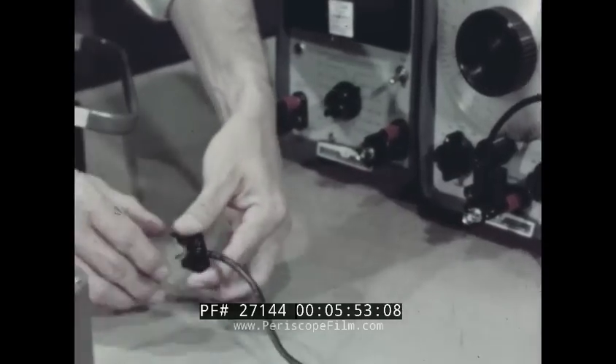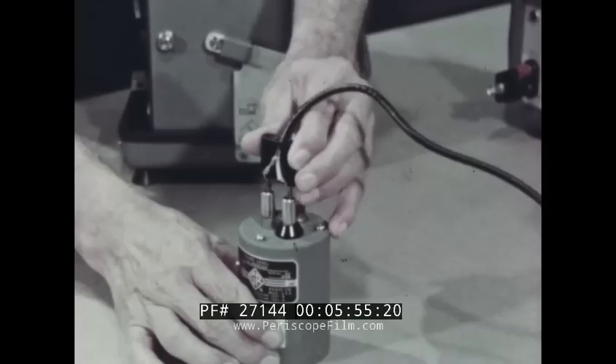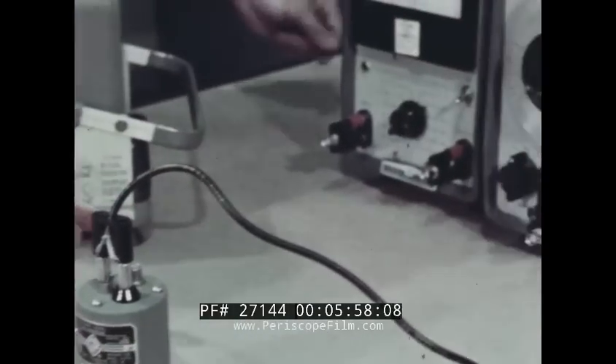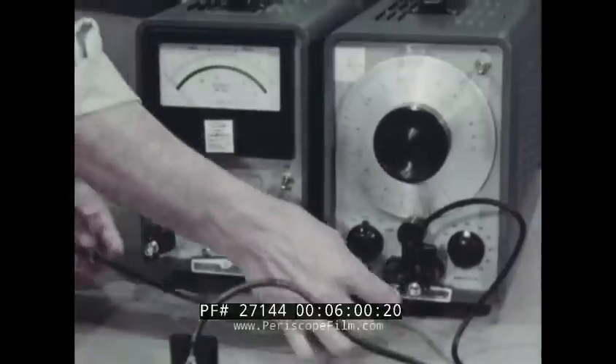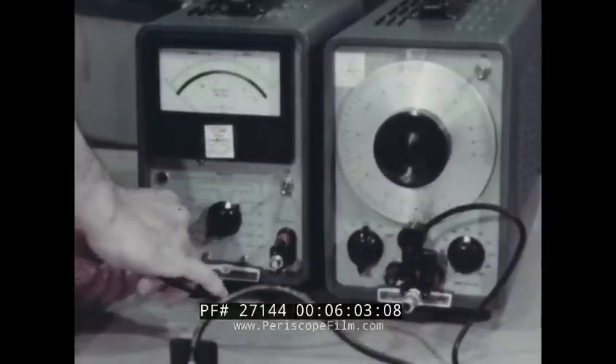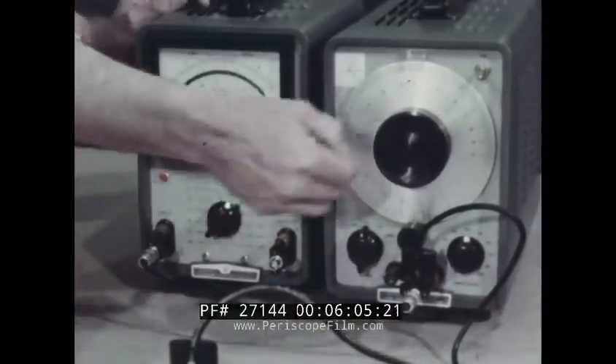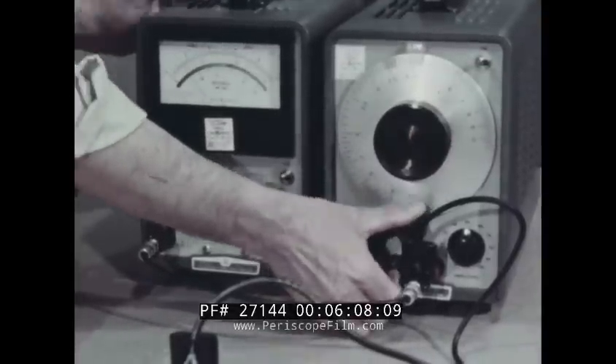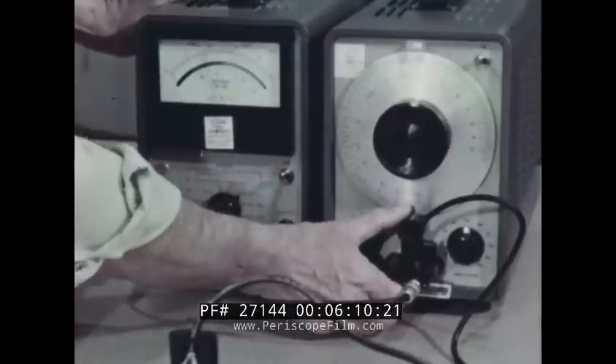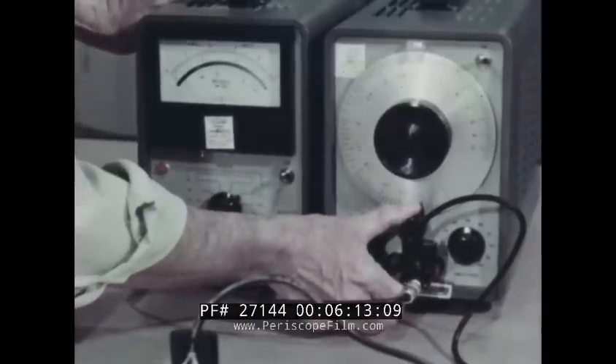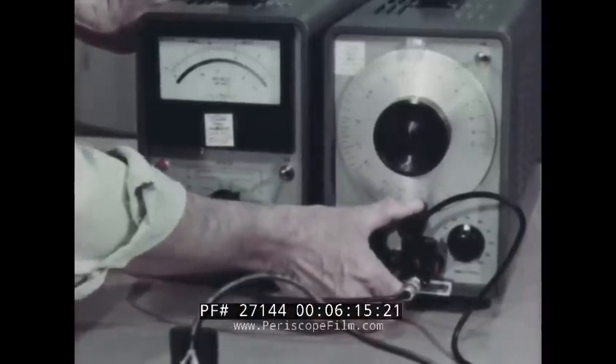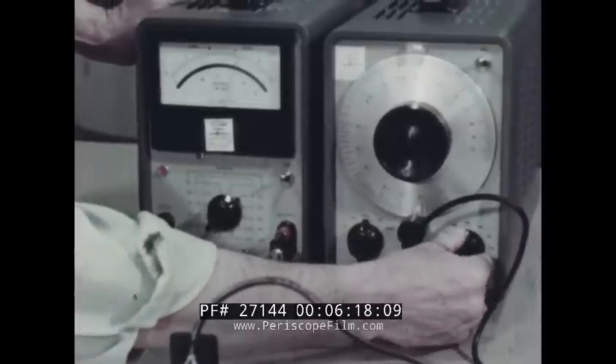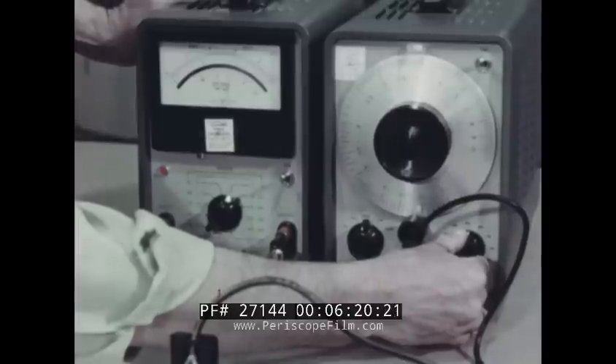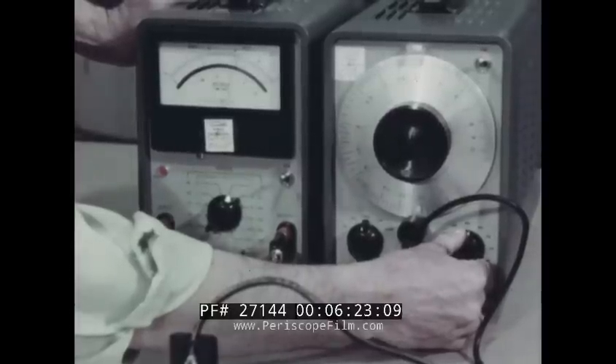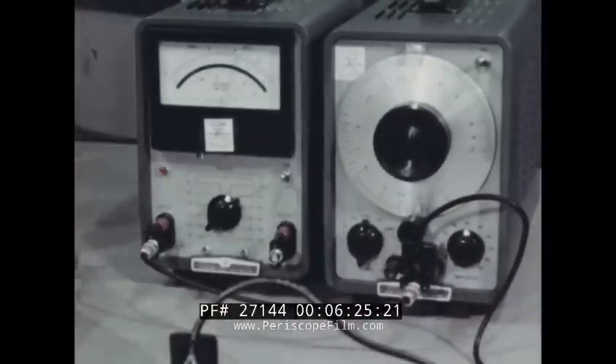Connect the calibrator to the 600 ohm output terminals of the oscillator. Connect the VTVM to measure the oscillator output and adjust for the specified frequency and voltage. For accurate results, you've got to be sure the voltage is exactly as called for.